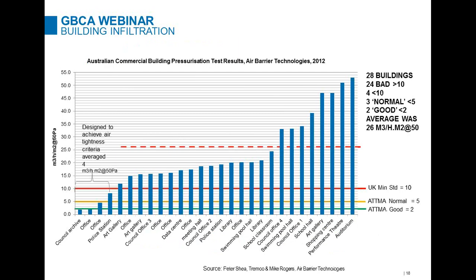Now this next slide is actually commercial building air tightness testing results provided by Mike Rogers from Air Barrier Technologies, which is one of the companies that does blower door testing. And what you can see here is that there is a range of performance. At the good end, you've got some down at that 2 level on the left-hand side, an archive and an office that are actually the only ones hitting what's considered to be good. And that's actually a really great achievement, that there are some in that group that are hitting that. One just under 5, so that's still quite good. A police station, which was I think about 7.